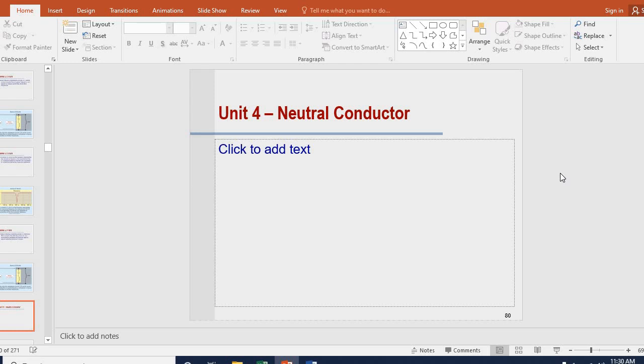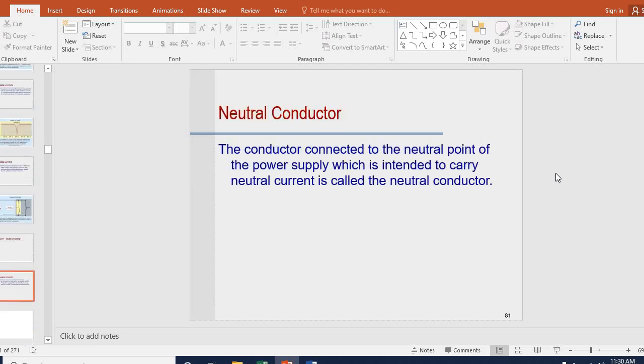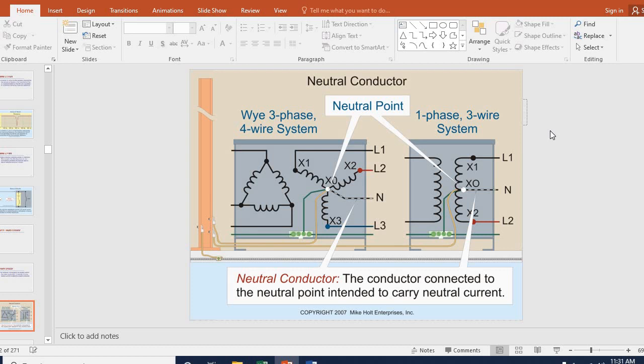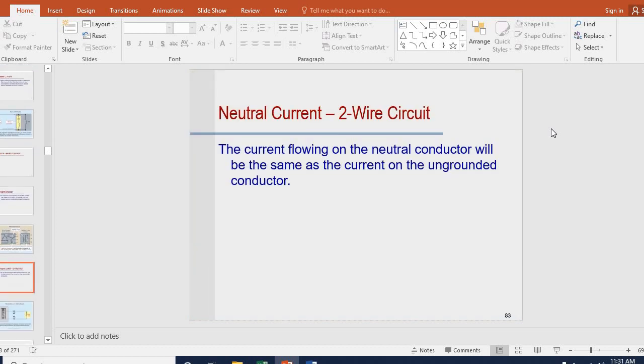All right, we're into neutral conductors. The conductor connected to the neutral point of the power supply, which is intended to carry a neutral current, is called the neutral conductor. If it's carrying current, it's got to be insulated. So there's your difference between a current carrying conductor and a ground. The ground doesn't have to be, but you also don't want current on your ground. So it's important to keep separated a neutral conductor and a grounding conductor. The current flowing on the neutral conductor will be the same as the current on the ungrounded conductors.